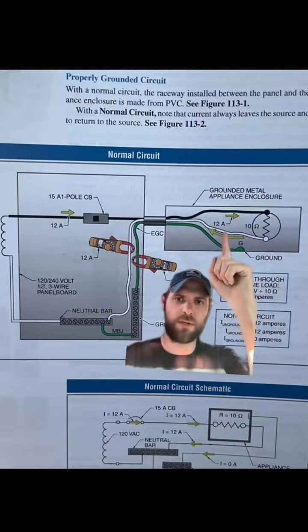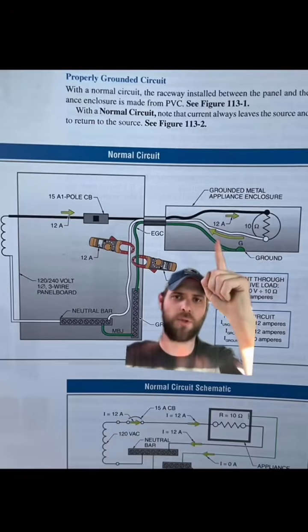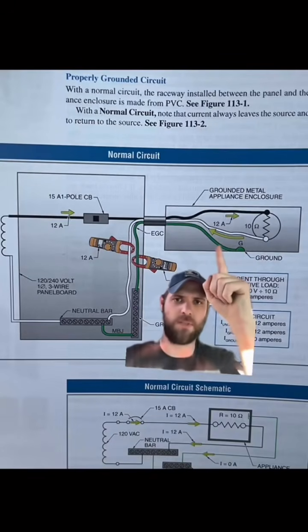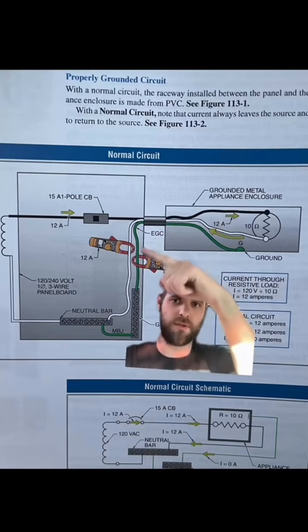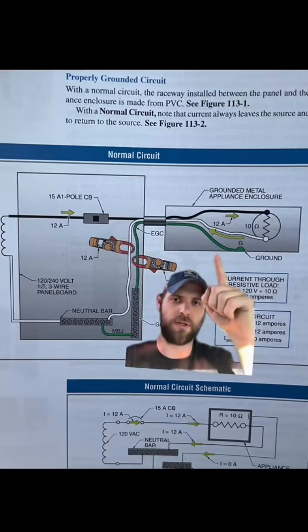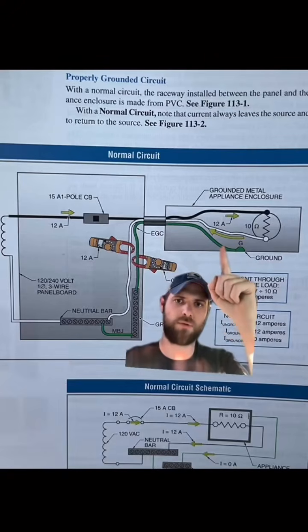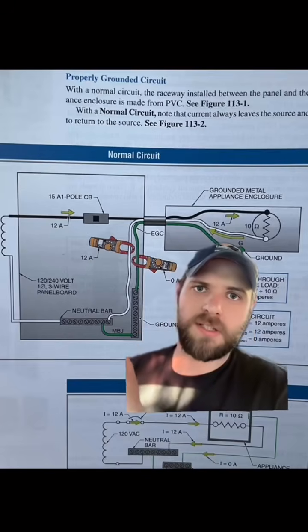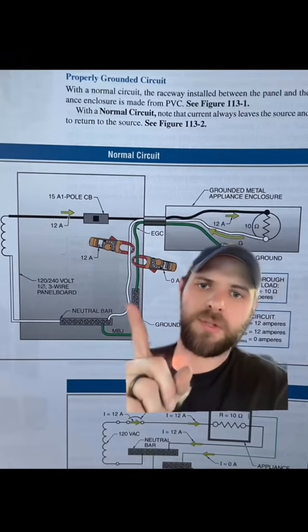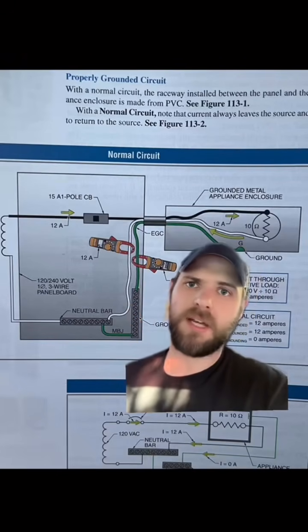So why can't we bond our neutral and equipment grounding conductor together more than once on the same system? The answer is simple. Doing so would put your equipment grounding conductor in parallel with your neutral. By doing so, you will have effectively turned your equipment grounding conductor into a current carrying conductor. What that means is that the neutral current will be split between the two conductors in proportion to the resistance of each conductor. The most common mistake I see where this is concerned is handymen and homeowners installing a green bonding screw inside of a sub panel, not realizing that that's an issue.